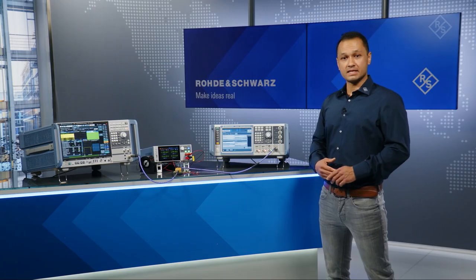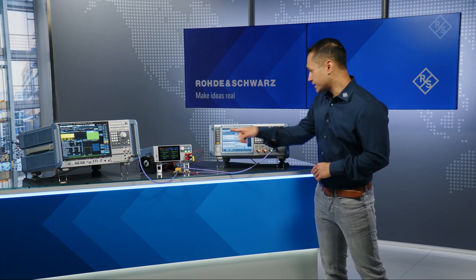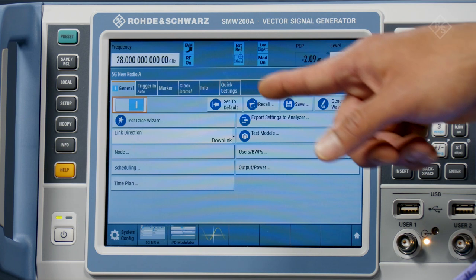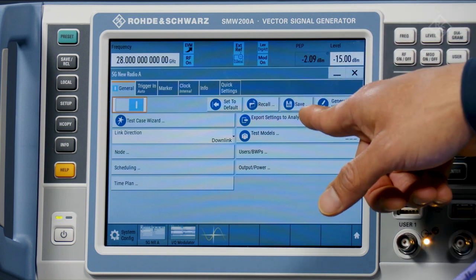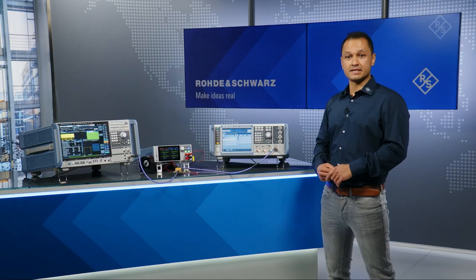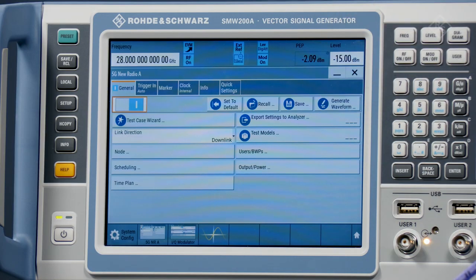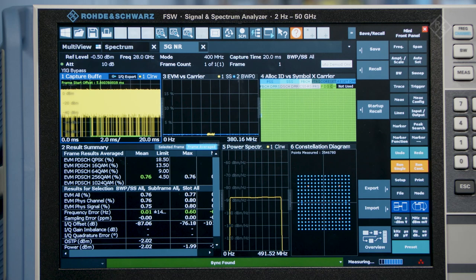After the signal has been configured on the signal generator, we can directly export the setting to the FSW signal analyzer for demodulation. Alternatively, the signal generator configuration settings can also be queried by the signal analyzer. The setting transfer between the generator and the analyzer allows you to demodulate the signal and measure EVM without any further configuration effort.